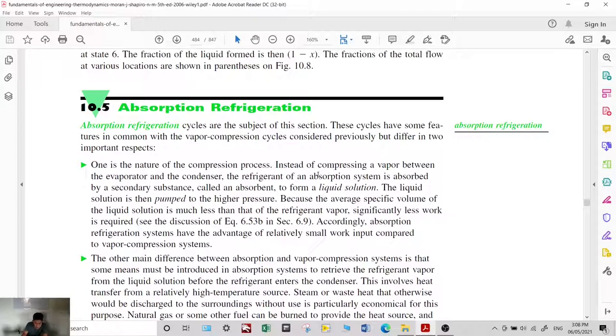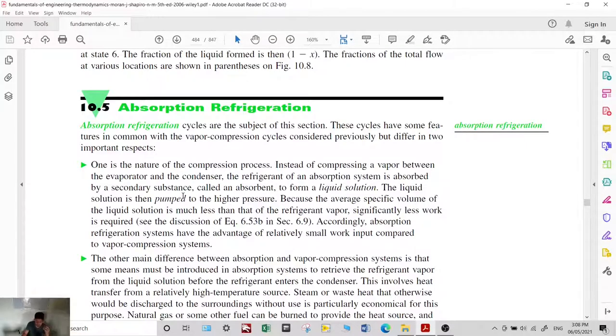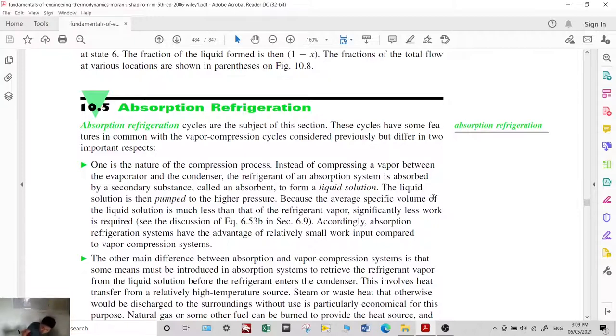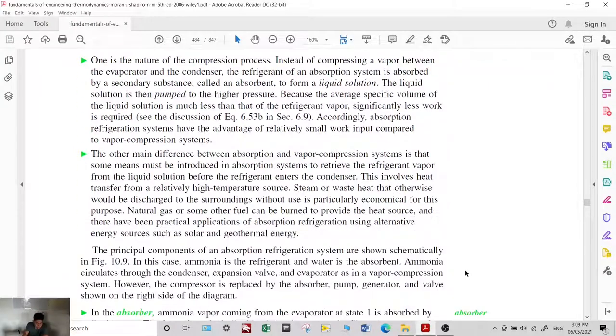Instead of compressing a vapor between the evaporator and the condenser, in an absorption system the refrigerant is absorbed by a secondary substance. The refrigerant is absorbed into liquid by an absorbent, and the liquid solution is pumped to higher pressure. Since the average specific volume of a liquid solution is much less than that of the refrigerant vapor, significantly less work is required. Accordingly, absorption refrigeration systems have the advantage of relatively small work input compared to vapor compression systems.